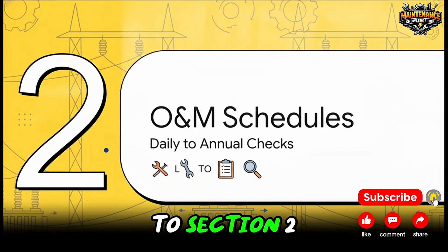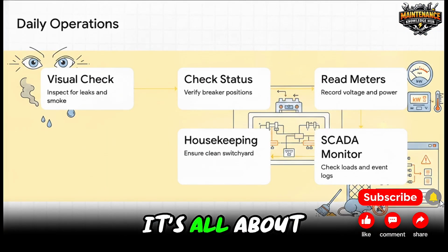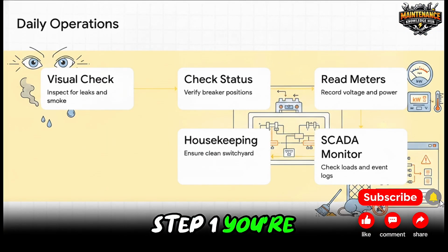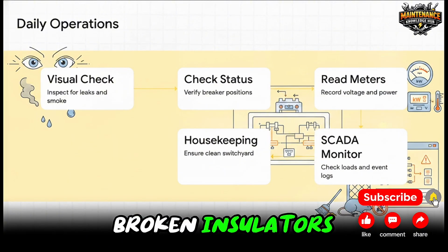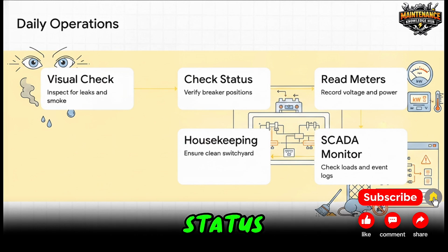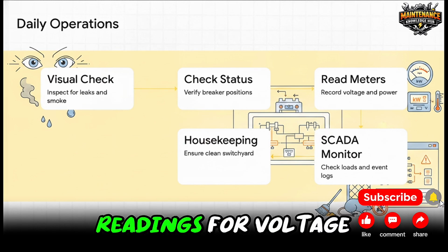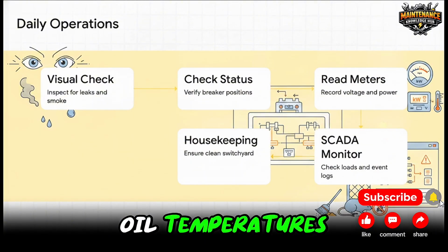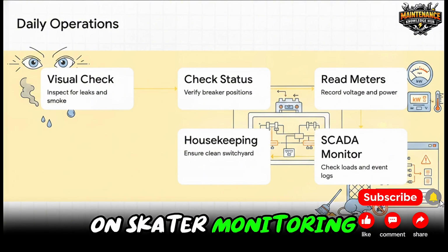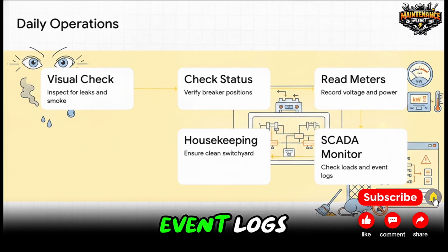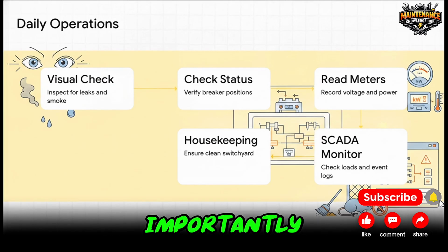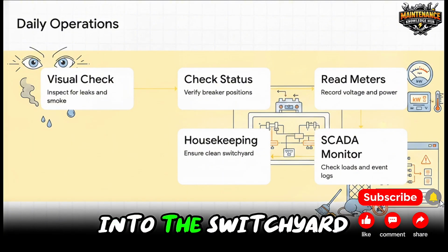Moving right along to Section 2, Operations and Maintenance Schedules. So, daily operations, it's all about active urgency. Step 1, you're literally opening your eyes and hunting for oil leaks, smoke, or any broken insulators. Step 2, you verify the equipment's status and those breaker positions. Step 3 is all about recording vital signs, meter readings for voltage, active power, and oil temperatures. Step 4 relies on SCADA monitoring to verify overall system loads and check the event logs. And Step 5 is just basic housekeeping, making sure drainage is clear and, importantly, that no local wildlife has managed to sneak into the switchyard.